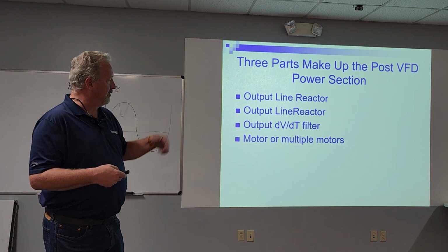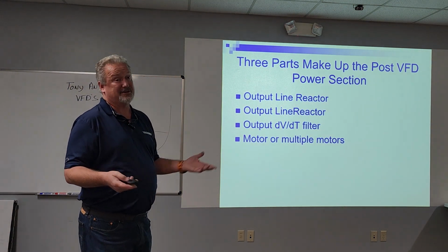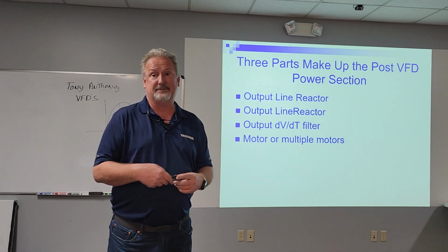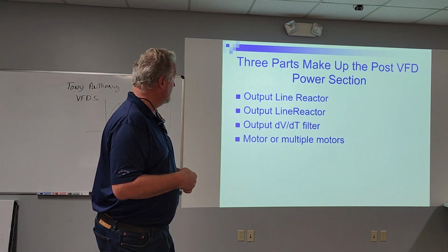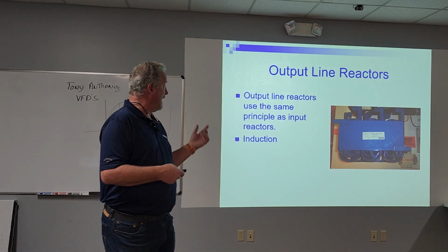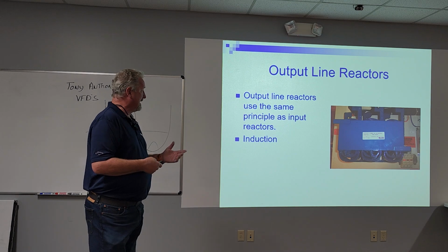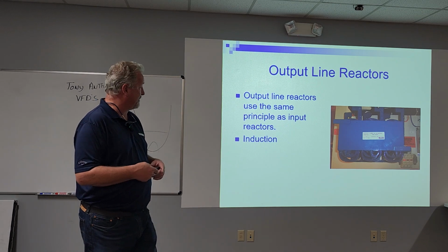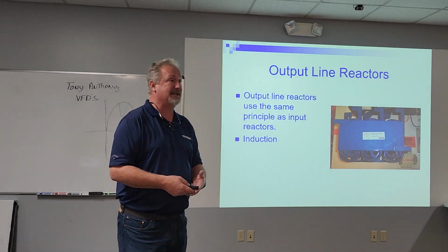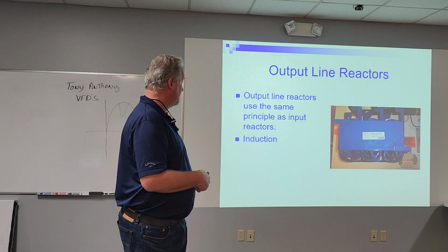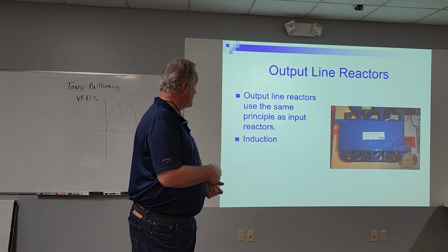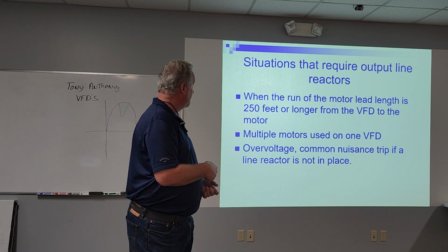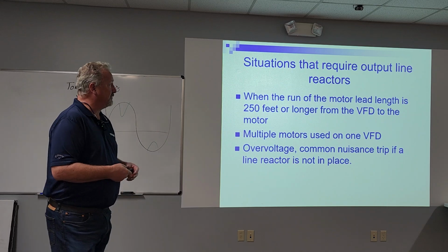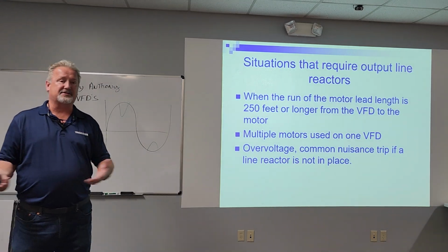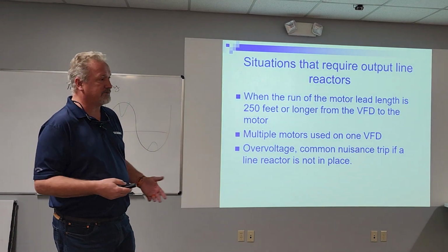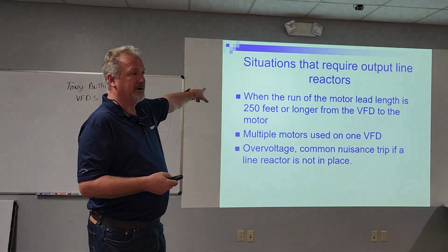We're going to talk about motors and multiple motors, because a lot of people don't realize you can actually run several motors off one drive. The drive doesn't care. We'll talk about that here. The output line reactor not only uses the same principle, it's the exact same device. It's the same part, just where we use it. And it's basically a one-to-one transformer. We're using induction. This says 250. Some manufacturers say 150. Some say 200. This is really motor dependent.